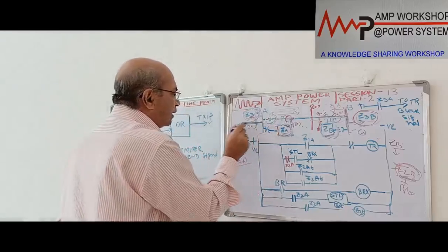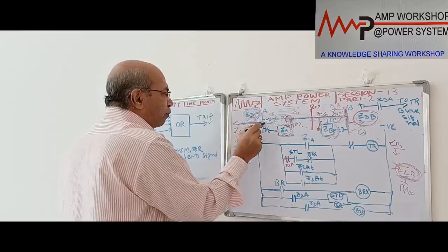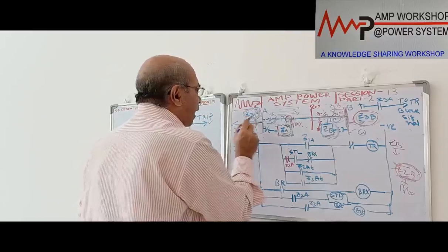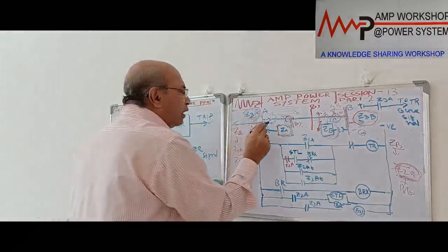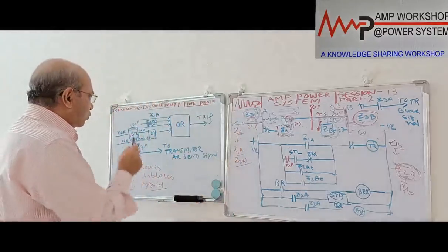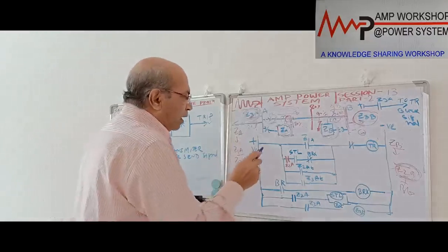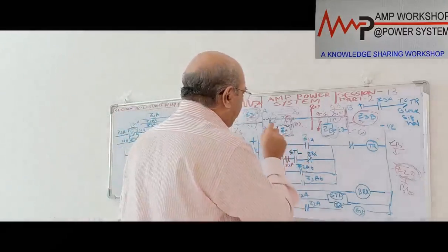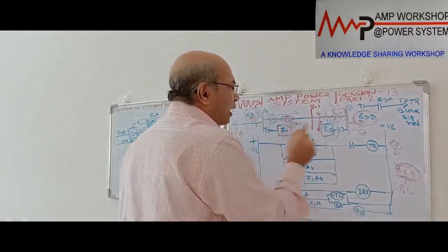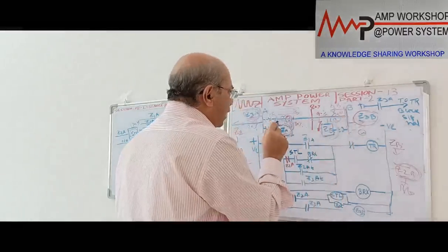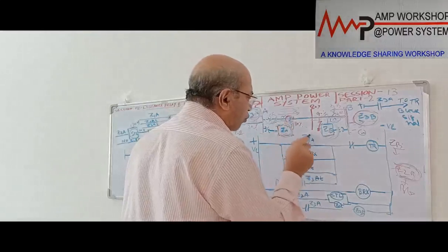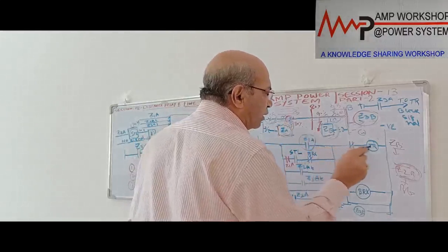For this side fault, when zone 3 is operated, the fault is on the next line, on this side. So when Z3 operates, after the definite time delay, it will trip this breaker as well, if this previous expedite trip does not work. So that is what we have drawn over here. You see here, Z1: we have considered the fault is near to this station, within 10% of station A, and this is the remote end. So the near end fault is near station A. When the near end fault is there, zone 1 unit immediately operates, and this is a trip.